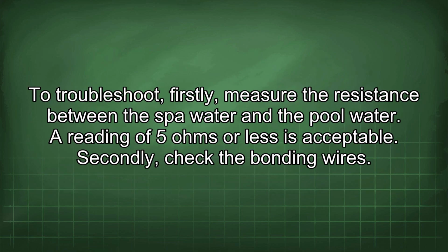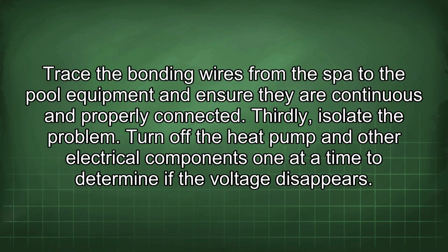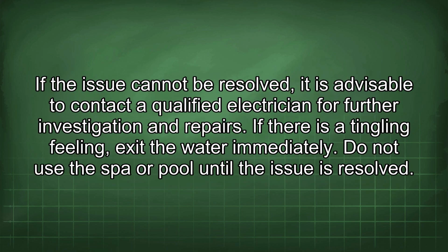To troubleshoot, firstly, measure the resistance between the spa water and the pool water. A reading of 5 ohms or less is acceptable. Secondly, check the bonding wires. Trace the bonding wires from the spa to the pool equipment and ensure they are continuous and properly connected. Thirdly, isolate the problem. Turn off the heat pump and other electrical components one at a time to determine if the voltage disappears. If the issue cannot be resolved, it is advisable to contact a qualified electrician for further investigation and repairs.